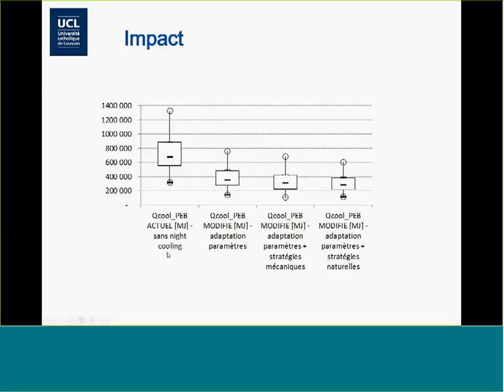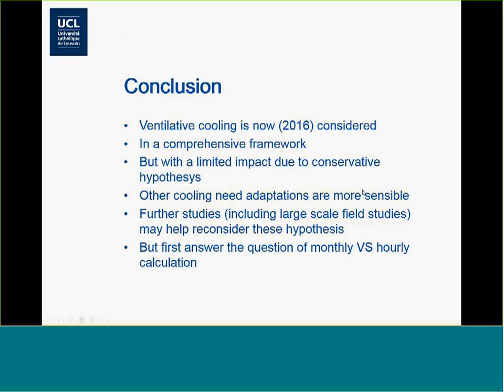So about the impact of all those changes, in this figure you have the cooling need for a set of buildings. I don't describe the sets, not very consistent. There is just a large set of typical office buildings with various kinds of skins, various kinds of shading coefficients and thermal mass. And we have quite a large panel. What we see when we make the changes regarding outside temperatures, indoor temperatures, and intermittence, we have quite a large impact, and that's one part of our job. And when we go further and add either mechanical intensive ventilation or natural intensive ventilation, we still go further in the lowering of the cooling loads, cooling needs, but it's much less important than the changes we've made on basic hypotheses such as temperature and intermittence.